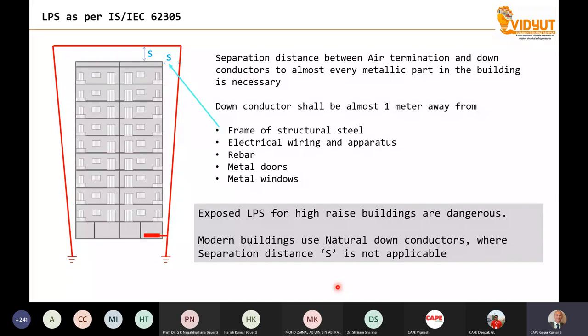And the recommended practice for high-rise buildings is to use the steel rebar or the natural components for the purpose of lightning protection. So this is, I would say, a small introduction about what exactly the Indian standard says. The Indian standard says there shall be a grid at the top, probably a few rods depending upon your roof, then several down conductors, an earthing system, and you have to make an equipotential bonding system. You have to have SPDs and so on. This is a very well designed lightning protection system.